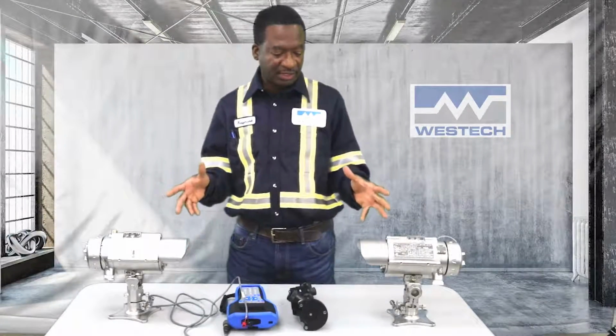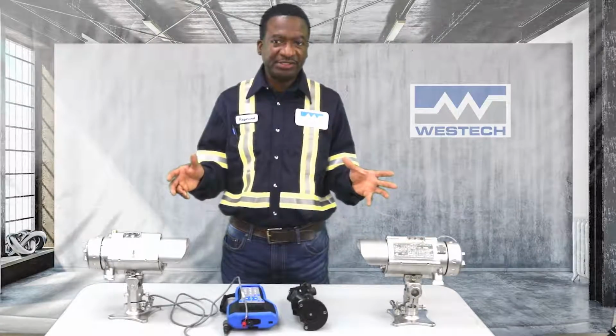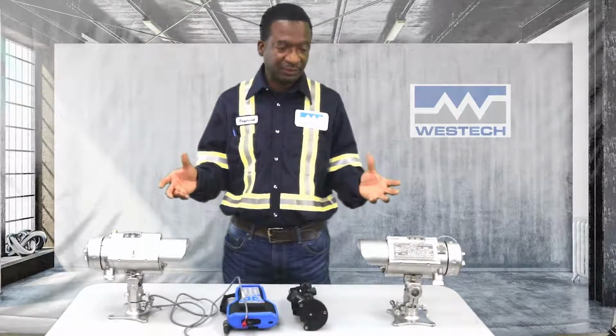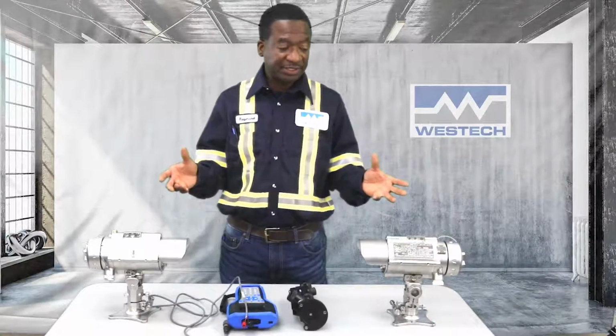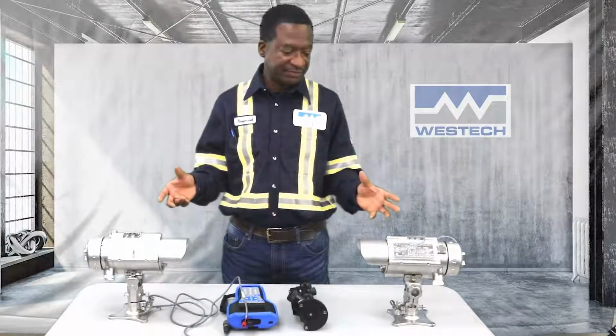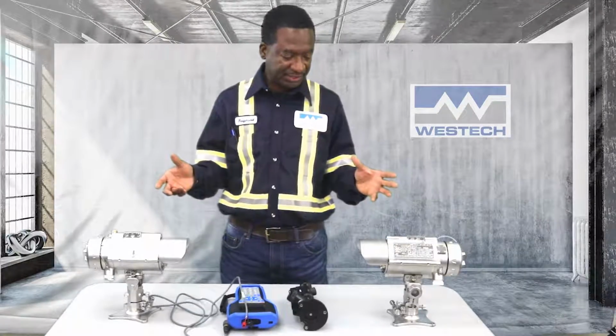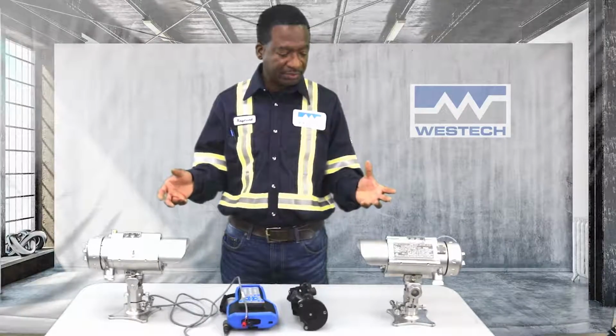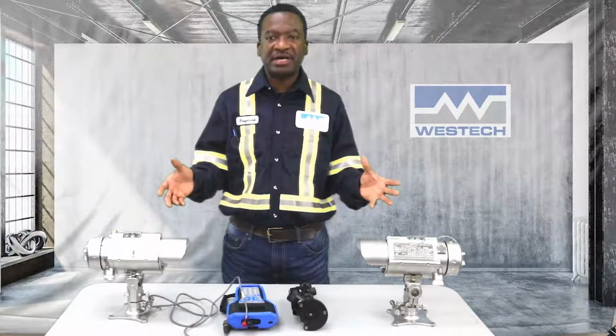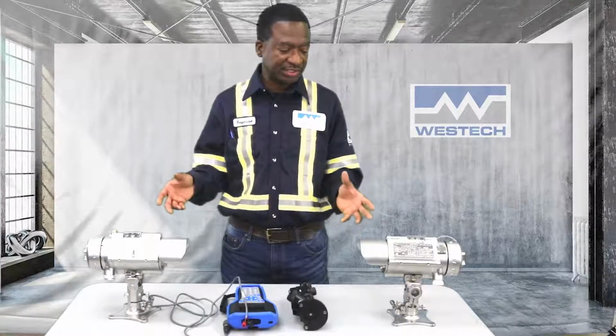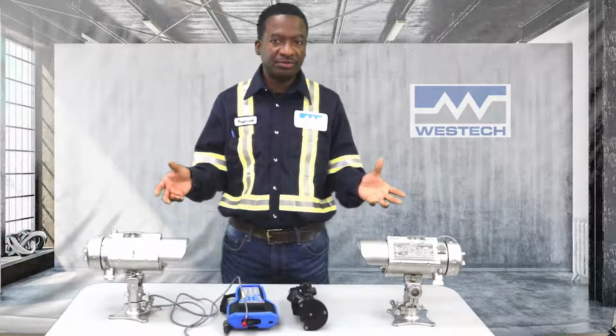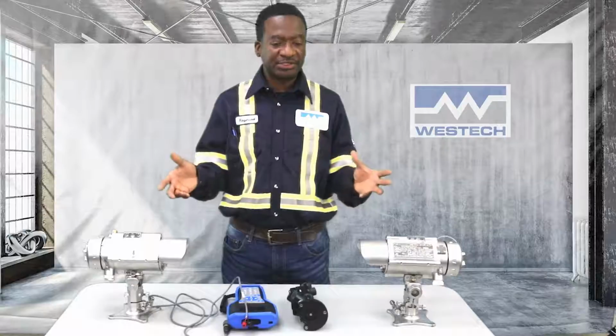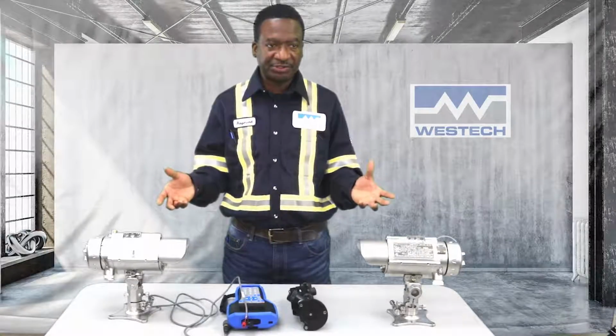The detection system operates on a 18 to 32 VDC voltage. The operating temperature is minus 55 to plus 65 degrees C. So the system is quite robust and it will not be affected by harsh weather conditions like rainfall, snow, or high temperatures as long as it's within the operating temperature range.